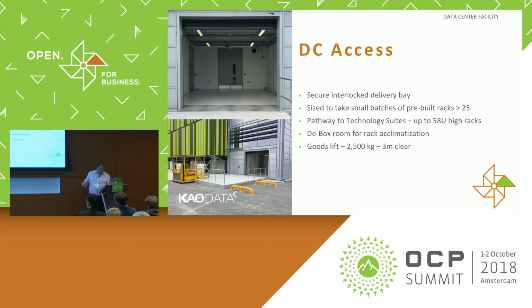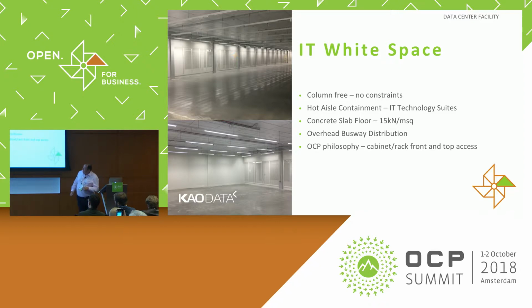The other thing we picked up on is removal of the raised floor, something we've been developing through projects at my previous job. With OCP racks and their weight, having that raised floor element just creates a problem in terms of distribution of equipment and loads. So we've stripped out the raised floors and got a sealed concrete floor, rated at 15 kilonewtons per square metre, which easily supports 3,300 pounds of IT load, or 1,500 kilograms. Everything within the space is arranged to give you the front access, top access that OCP is based around.